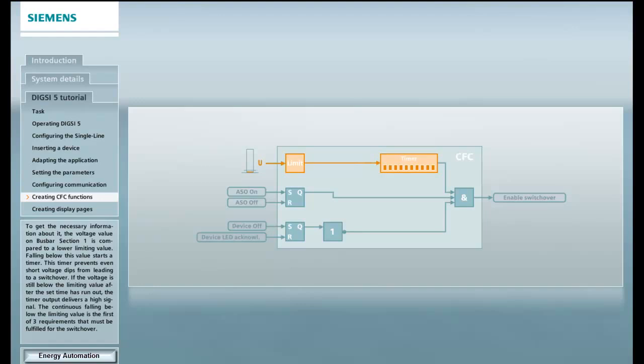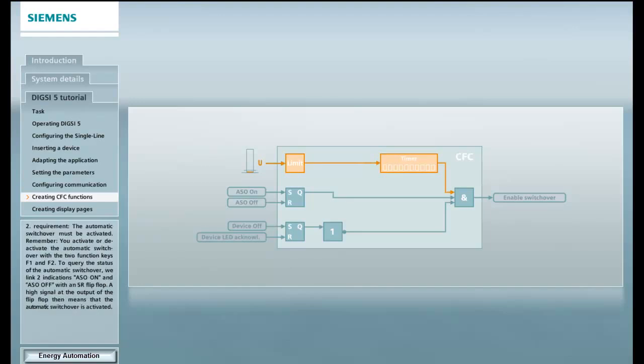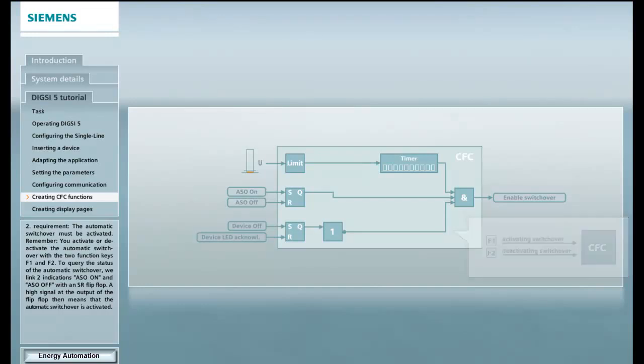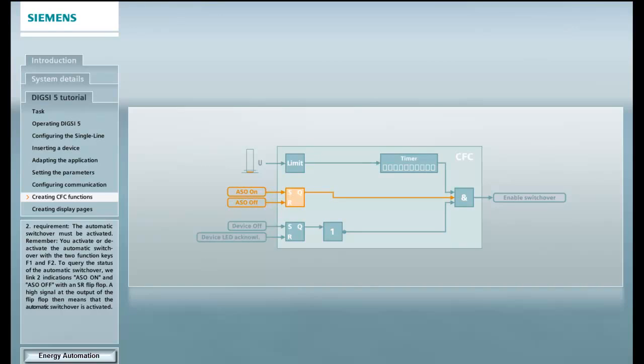This timer prevents even short voltage dips from leading to a switchover. If the voltage is still below the limiting value after the set time has run out, the timer output delivers a high signal. The continuous falling below the limiting value is the first of three requirements that must be fulfilled for the switchover. Second requirement, the automatic switchover must be activated. Remember, you activate or deactivate the automatic switchover with the two function keys F1 and F2. To query the status of the automatic switchover, we link two indications ASO on and ASO off with an SR flip-flop.